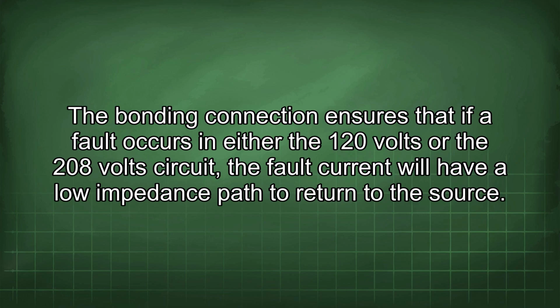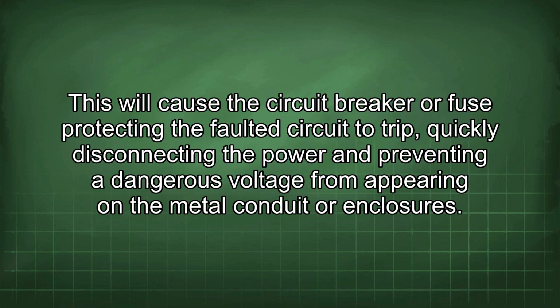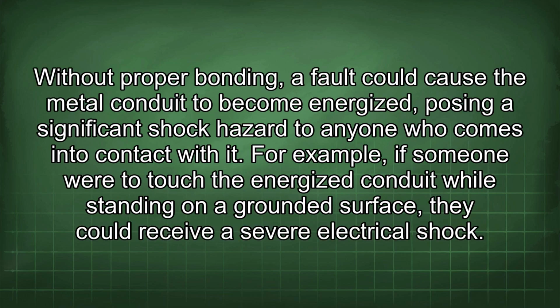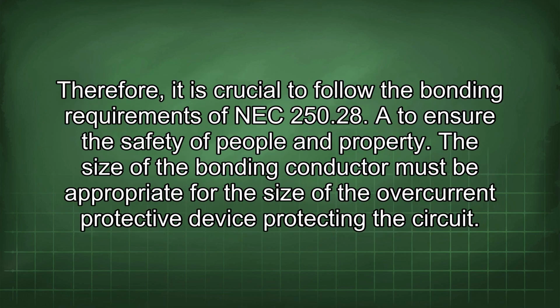The bonding connection ensures that if a fault occurs in either the 120 volts or the 208 volts circuit, the fault current will have a lower impedance path to return to the source. This will cause the circuit breaker or fuse protecting the faulted circuit to trip, quickly disconnecting the power and preventing a dangerous voltage from appearing on the metal conduit or enclosures. Without proper bonding, a fault could cause the metal conduit to become energized, posing a significant shock hazard to anyone who comes into contact with it. For example, if someone were to touch the energized conduit while standing on a grounded surface, they could receive a severe electrical shock.